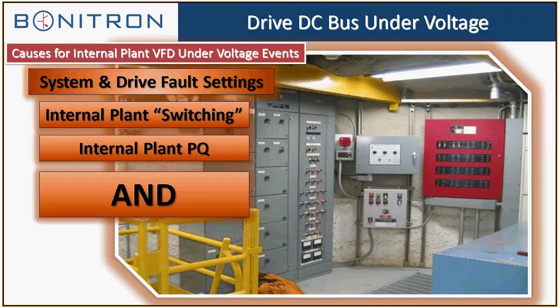Excuse me. You also have internal plant issues to deal with that can create ride-through events. System and drive fault settings: some drives have ride-through in them, and some have parameters that have to be disabled, like phase loss and things like that, but that's a very uncommon thing. Usually when you hook the ride-through up, it's pretty much plug and play and ready to go.